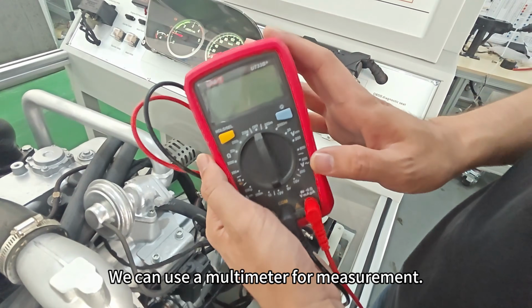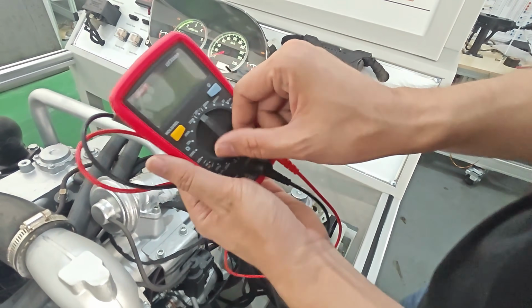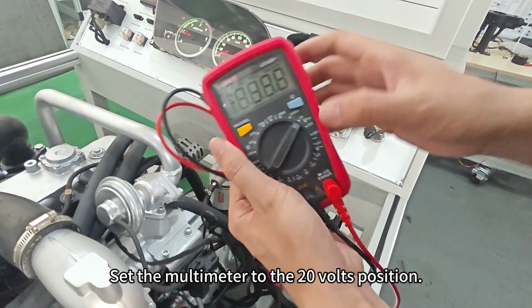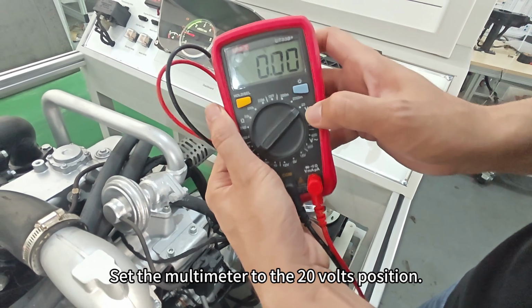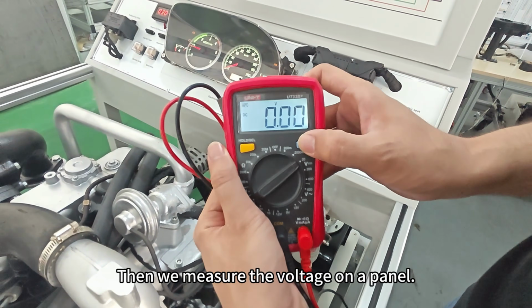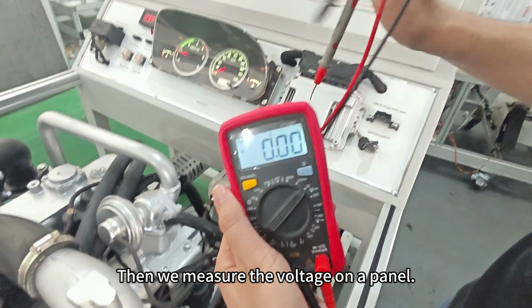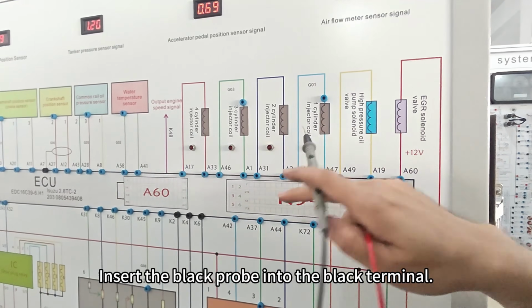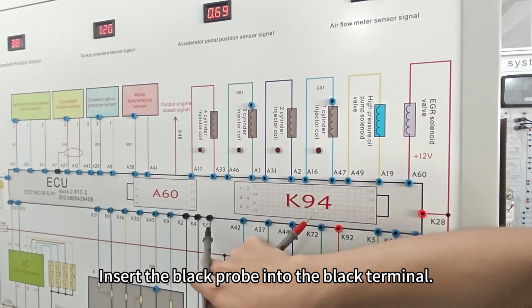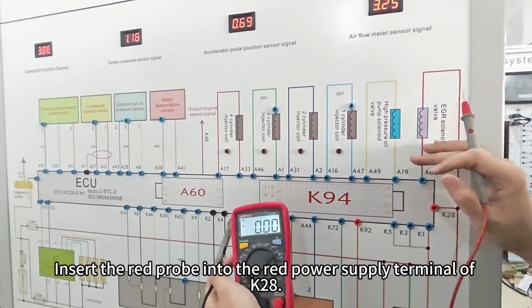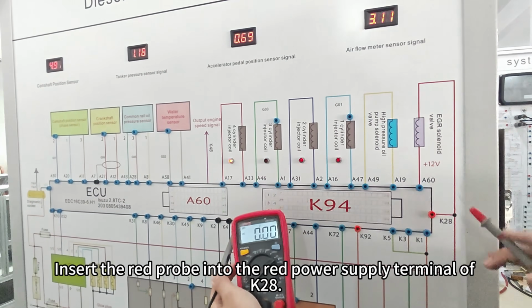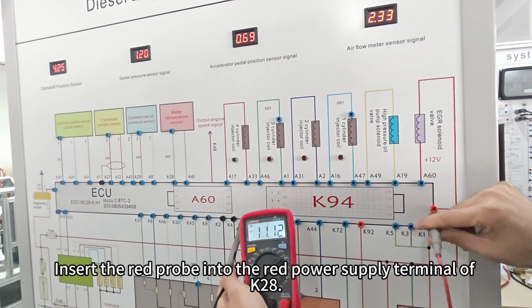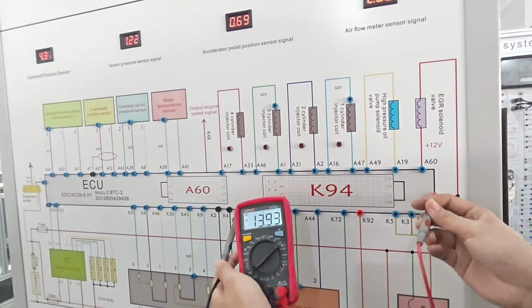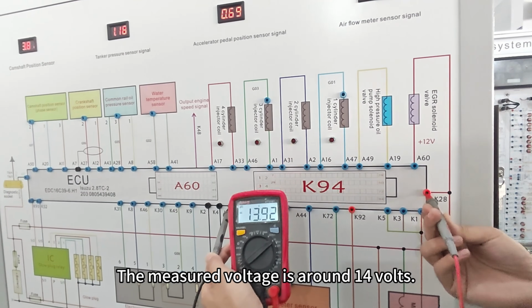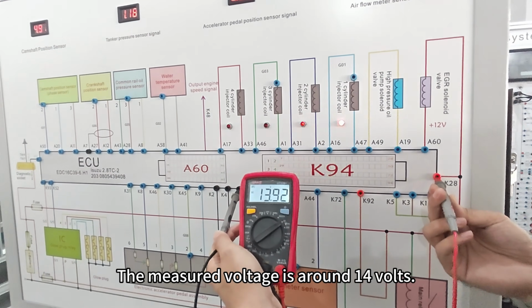We can use a multimeter for measurement. Set the multimeter to the 20 volts position. Then we measure the voltage on a panel. Insert the black probe into the black terminal. Insert the red probe into the red power supply terminal of K28. The measured voltage is around 14 volts.